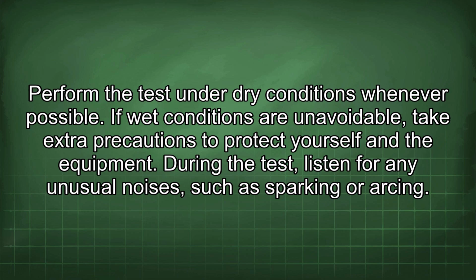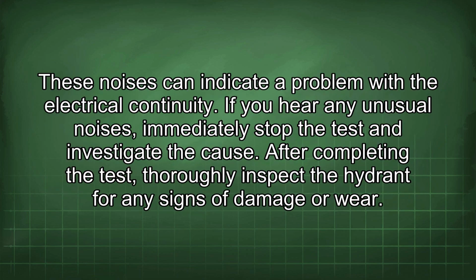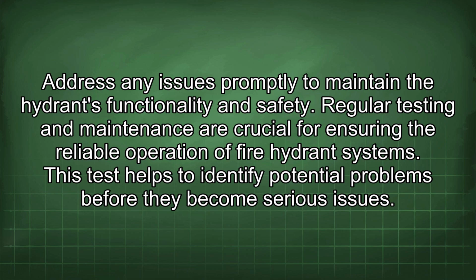During the test, listen for any unusual noises, such as sparking or arcing. These noises can indicate a problem with the electrical continuity. If you hear any unusual noises, immediately stop the test and investigate the cause. After completing the test, thoroughly inspect the hydrant for any signs of damage or wear. Address any issues promptly to maintain the hydrant's functionality and safety.